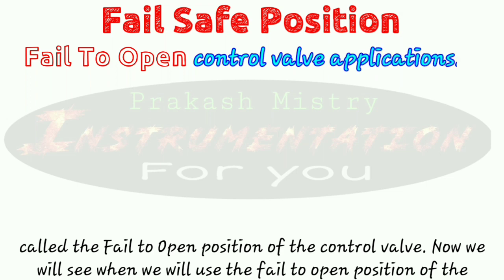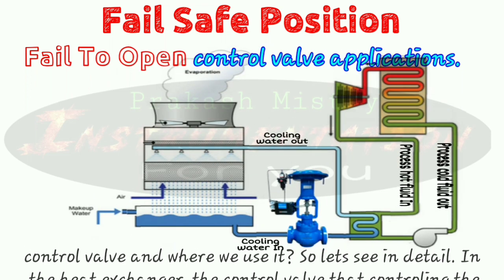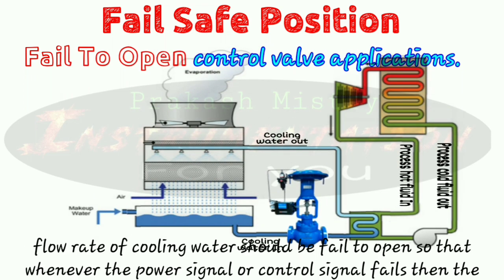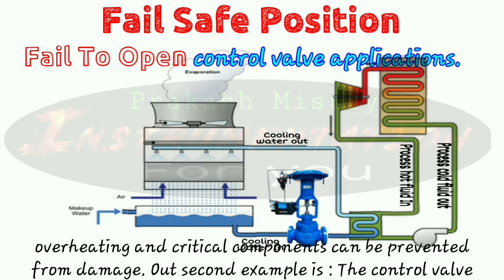Now we will see when and where we use the fail to open position of the control valve. In a heat exchanger, the control valve that controls the flow rate of the cooling water should be fail to open. So that whenever the power signal or control signal fails, the control valve enters the fully open position, and the remaining hot process fluid is cooled by the cooling water. Thus, overheating of critical components can be prevented from damage.